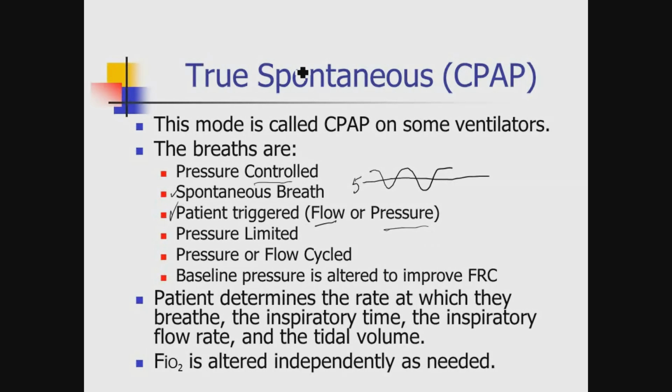No one else will. Because it's pressure controlled, it's also pressure limited. There's a maximum pressure that this is going to oscillate around. That's what we set. And we'll talk about the cycling mechanism in a half a second when I talk about pressure support. Key part is the patient determines everything involved.